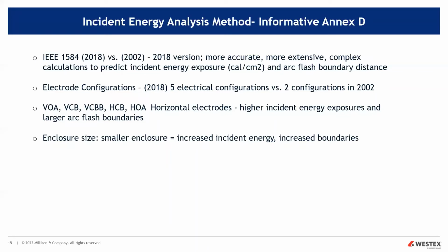So the 5 configurations, and a lot of you may already be familiar with this: VOA is vertical conductor in open air, VCB is vertical conductor in a box, VCBB is vertical conductor terminated in an insulated barrier in a metal box, HCB is horizontal conductor in a metal box, and HOA is horizontal electrodes in open air. And what they found is that if you have horizontal electrodes as opposed to vertical, higher incident energies are seen on the horizontal electrodes.